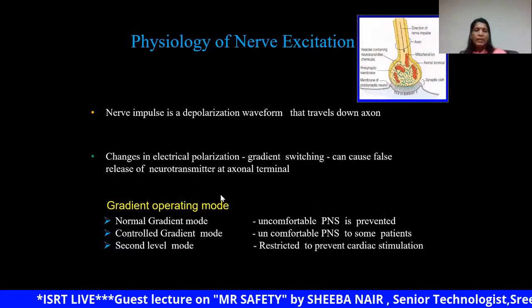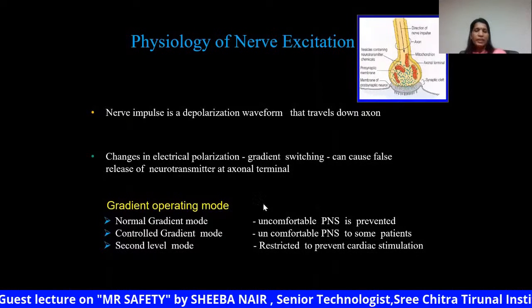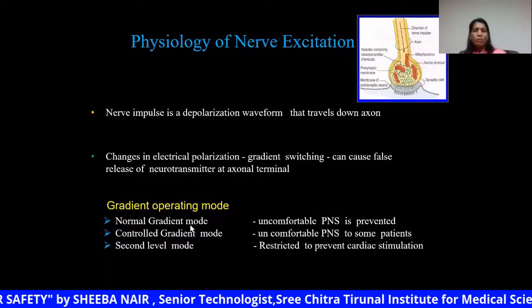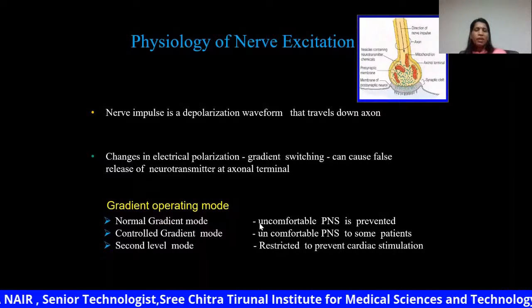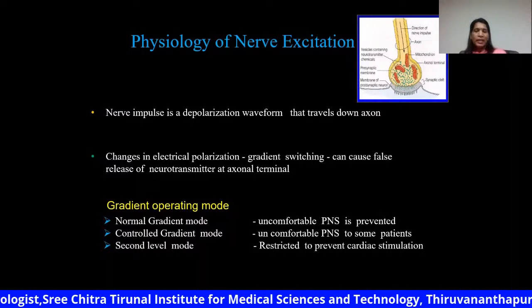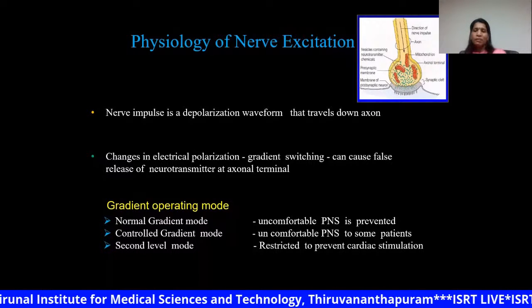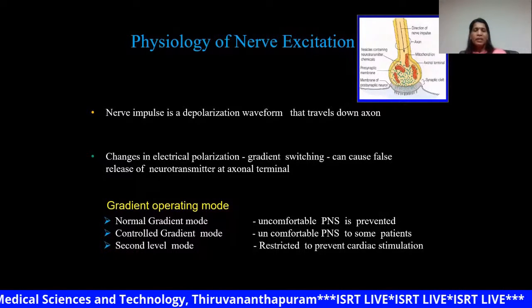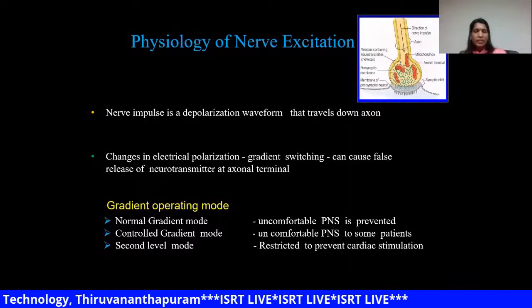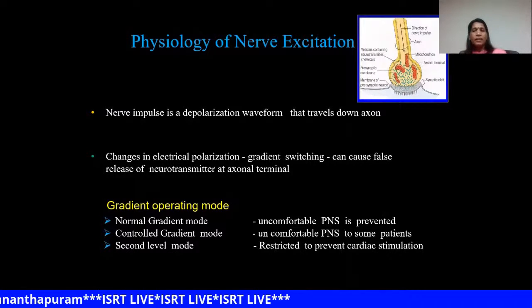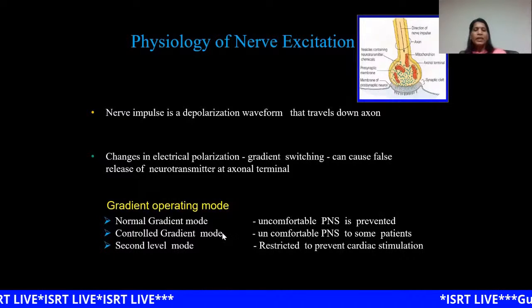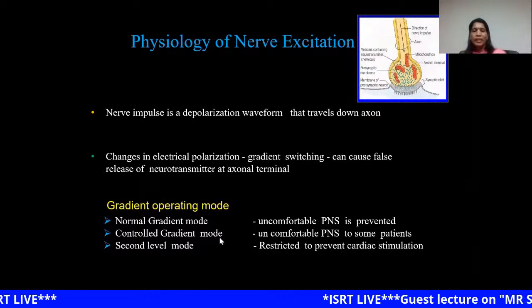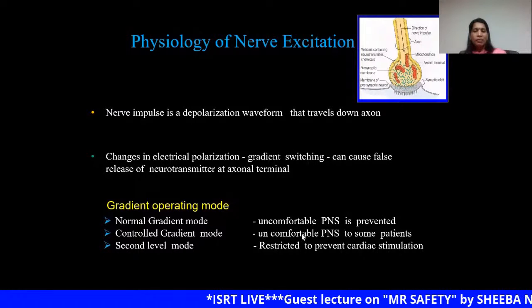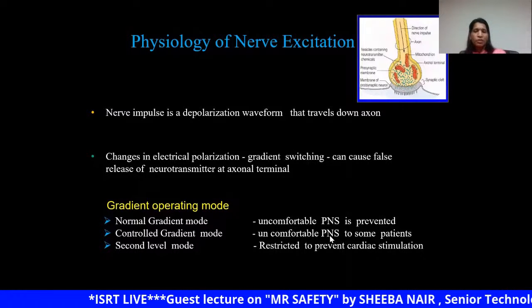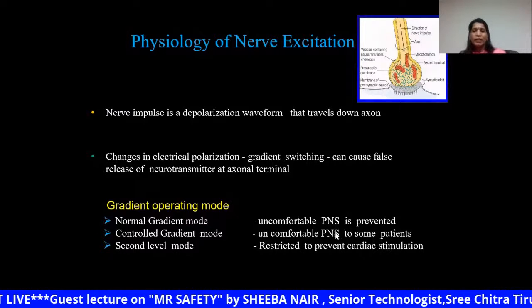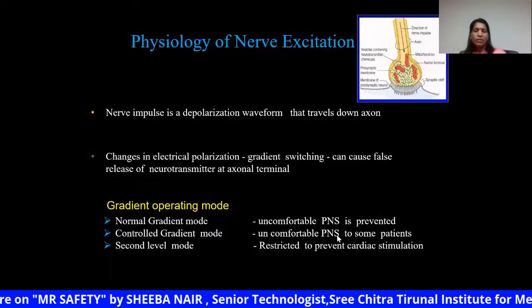So the system is provided with different operating modes for the gradients. Once you choose the normal gradient mode, the system will not permit any gradient switching that will produce uncomfortable peripheral nerve stimulation. It will be prevented. But in certain pulse sequences, such as the EPI sequence, you may need to enter the second mode, that is, the controlled gradient mode. Here the gradient switching will produce peripheral nerve stimulation, but it will not be severe. It will produce mild peripheral nerve stimulation.